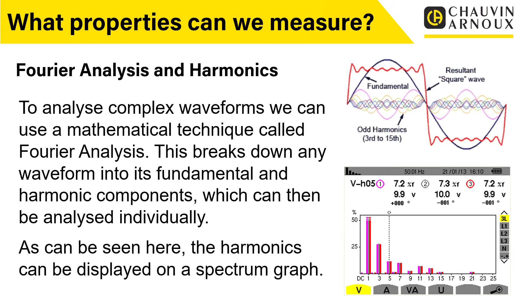So we're taking a waveform that's been distorted by these nonlinear loads, and we're using Fourier Analysis to plot it in a format that allows us to better diagnose what's going on. So harmonics are generally referred to as a multiple of the fundamental frequency. So the third harmonic is 3 times the fundamental, so it's 3 times 50 hertz or 150 hertz. If we're saying we've got third harmonic, we're actually seeing frequencies in there of 150 hertz, at 3 times the fundamental.